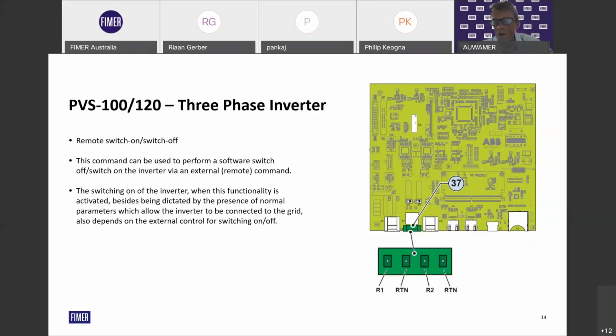The PVS 100/120 kilowatt three-phase inverters have a different board again. This is what we call a supervisory board, a COM board which sits horizontal on the AC section of the inverter down low. These are the terminals to connect to the remote on/off. It's quite simple — you wire from the Wattwatchers device to this. I'll show you a circuit diagram very shortly to make it more clear, but this is the way we wire to the inverter to activate the function.